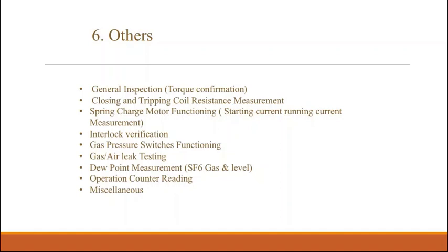Apart from this, here are some other tests we will be conducting. The first one is general inspection. General inspection is common for all. That is nothing but inspecting whether any crack is available in the insulator, or any dust. During transportation, whether any damage occurred, whether all bolts and nuts are tightened properly with the particular torque applied and there is a marking. Those things come under general inspection.